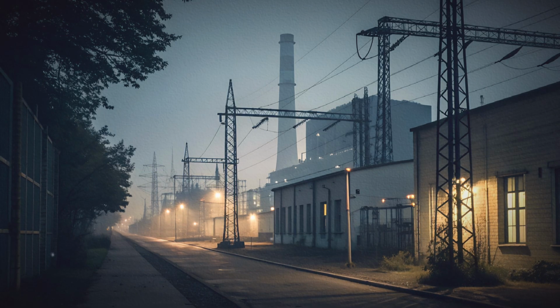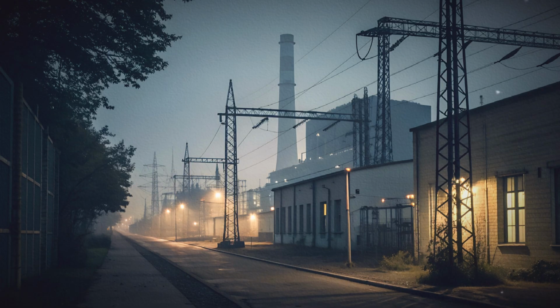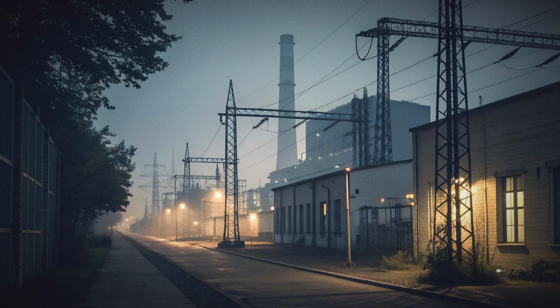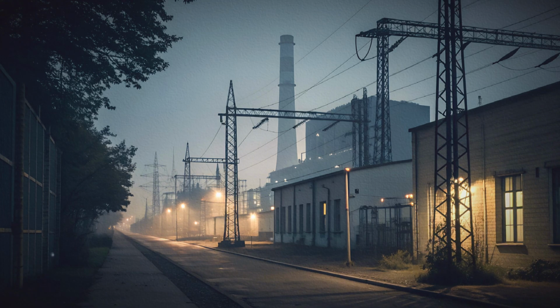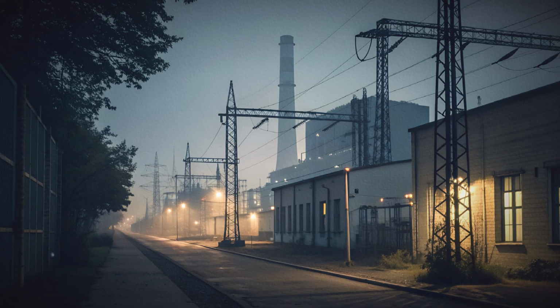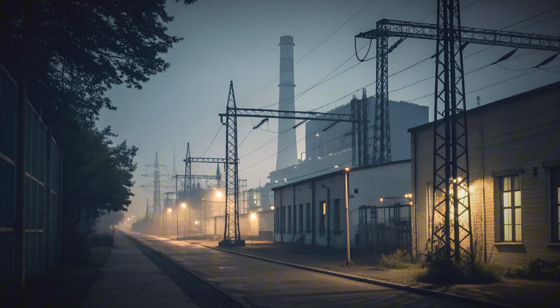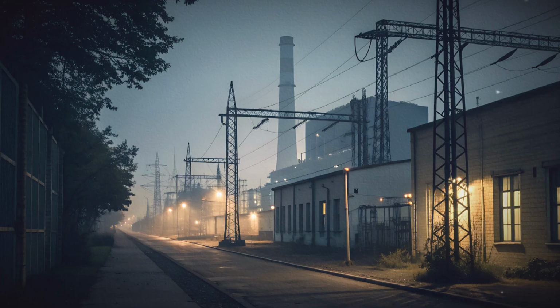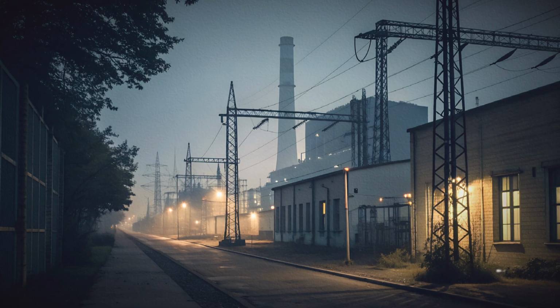A second layer of control adjusts generator set points over a longer time frame. This is often called centralized dispatch or automatic generation control. Centralized dispatch monitors system frequency and scheduled flows and issues adjustments to maintain a steady balance between generation and load. These adjustments are typically made in small steps, distributed among generators according to their capabilities and operational constraints.